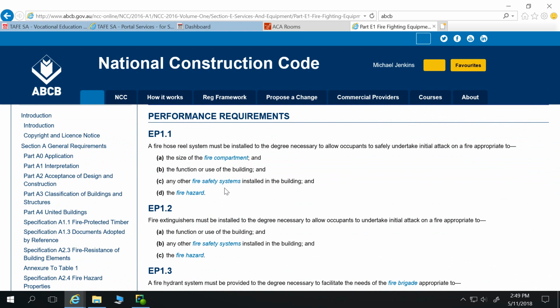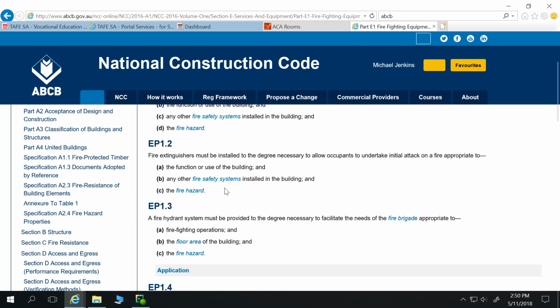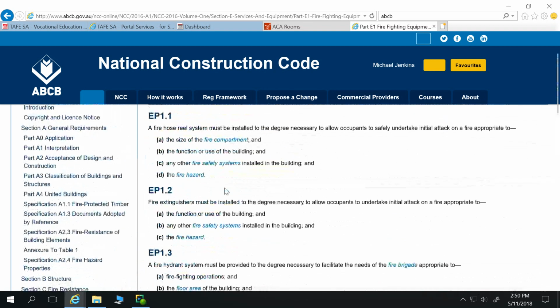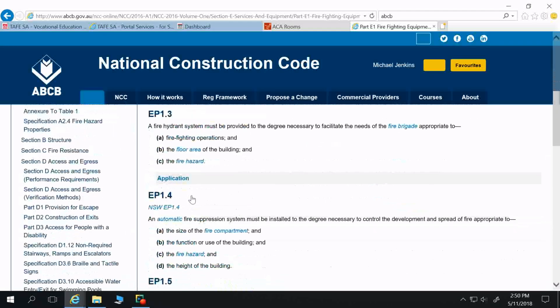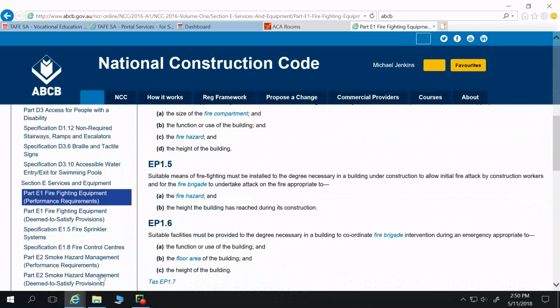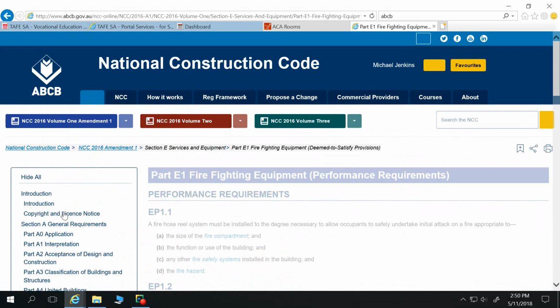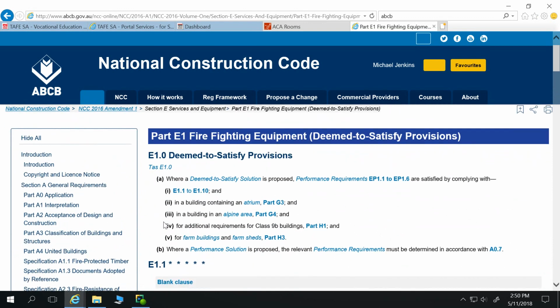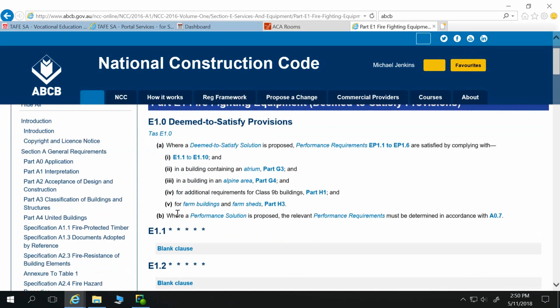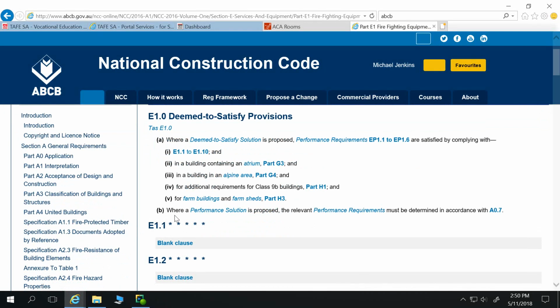So a fire hose reel system must be installed to the degree necessary to allow occupants to safely undertake initial attack on a fire appropriate to the size of the fire compartment, the functional use of the building, and any other fire safety systems installed in the building, and the fire hazard. So I know that's a bit of a how long is a piece of string type statement. So really I would say the most value in this is once again the deemed to satisfy provisions. So firefighting equipment deemed to satisfy provisions.